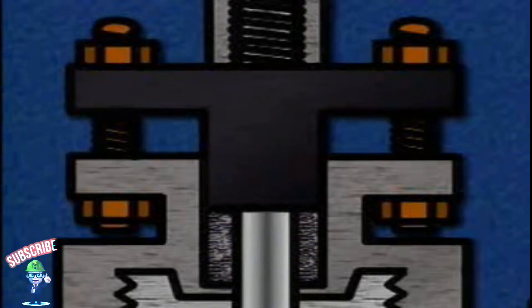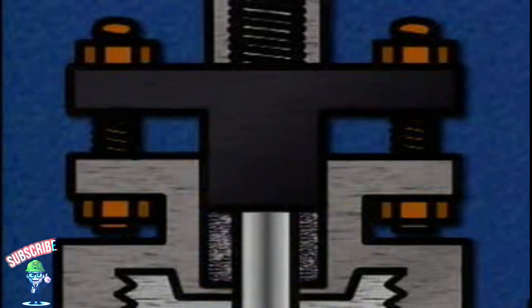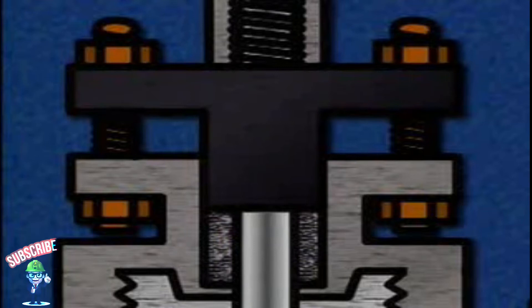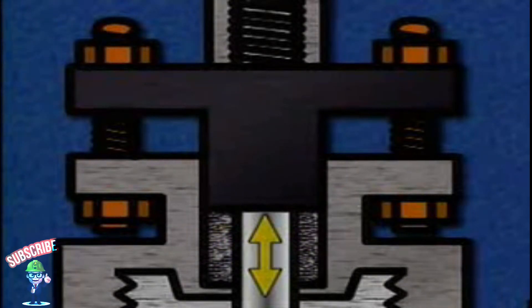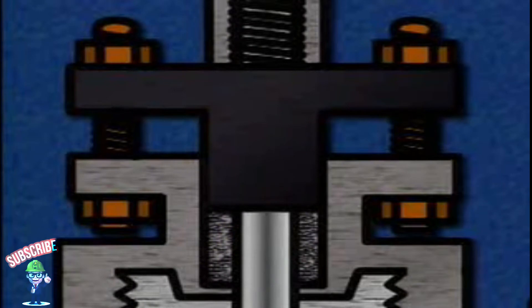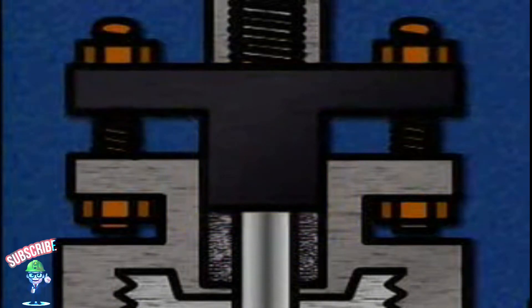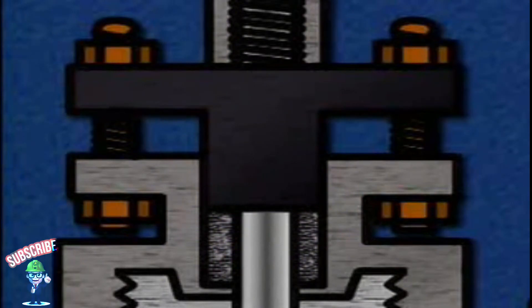At the point where the stem goes through the bonnet, there is a recessed area called the stuffing box. The stuffing box holds the packing. The purpose of the packing is to prevent fluid leaks from the interior of the valve, while allowing the stem to move freely through the bonnet. The packing is made of a material that can be compressed to form a tight seal around the stem. To compress the packing, a component called the gland follower is attached to the valve. The gland follower can be bolted or threaded onto the valve bonnet. When the gland follower bolts are tightened, the packing is compressed to prevent leaks.